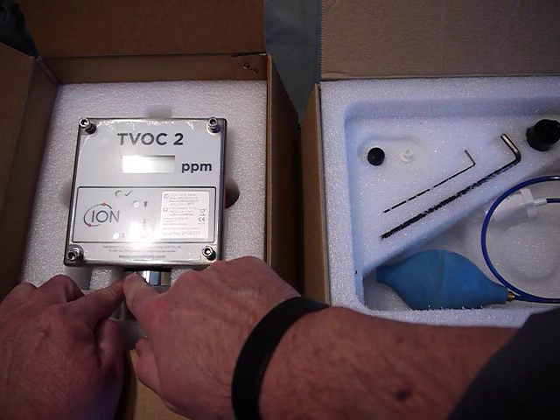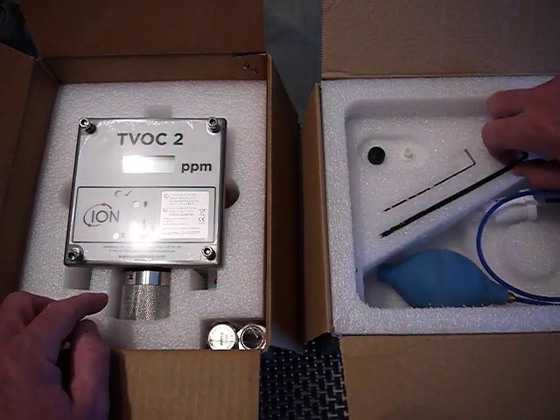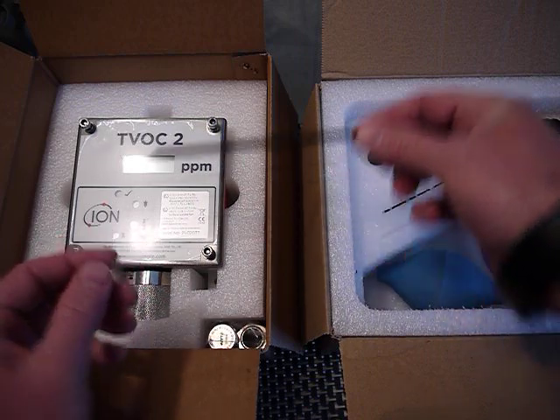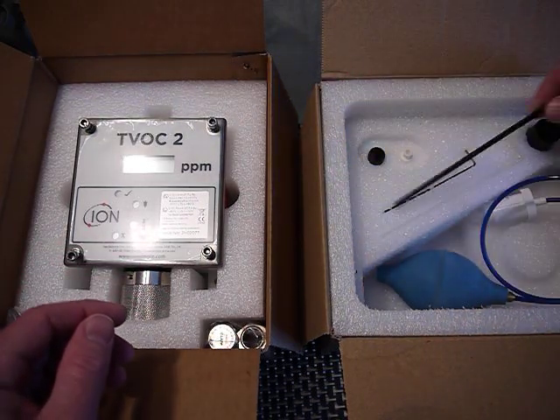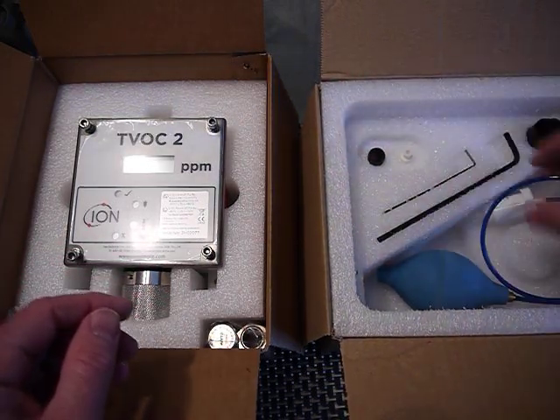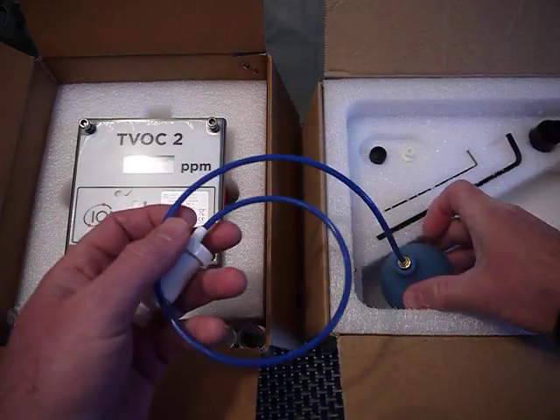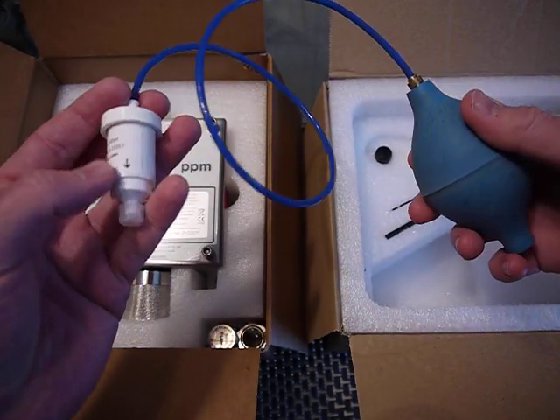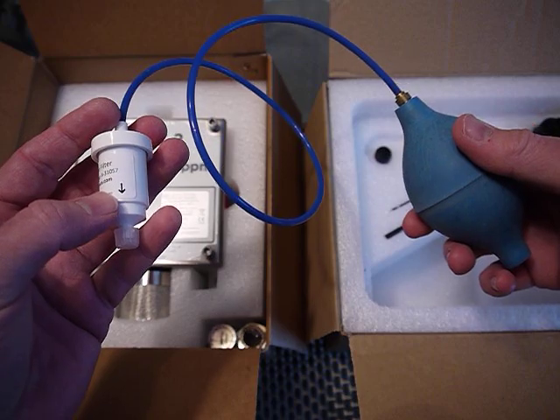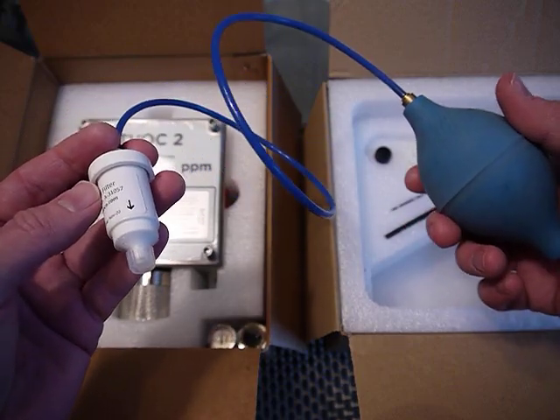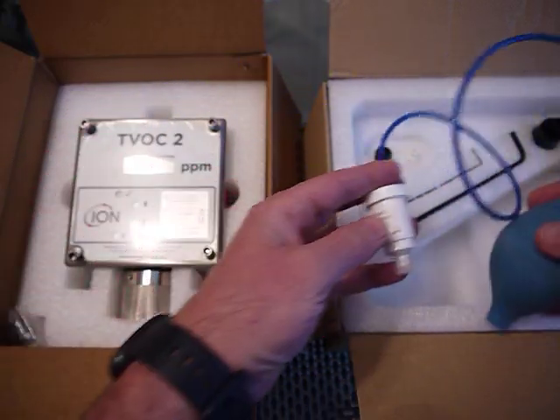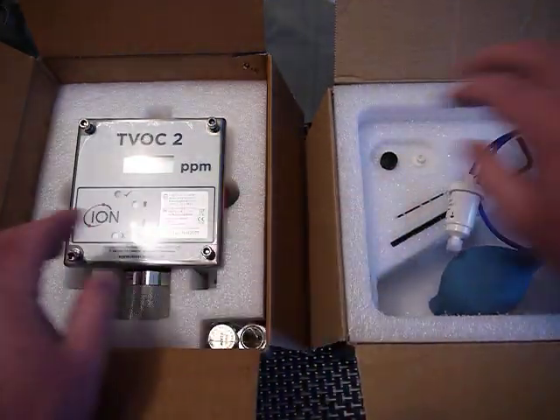Allen key here to get into the sensor, but more likely you may need to get into the unit itself, and that's a larger Allen key for these screws here. And for zeroing the unit, we have this hand aspirator and a carbon filter, so that would give zero air for checking the zero or calibrating the unit. So actually I'll show you some of this now.